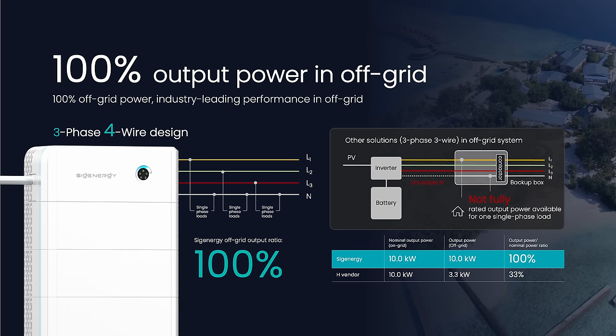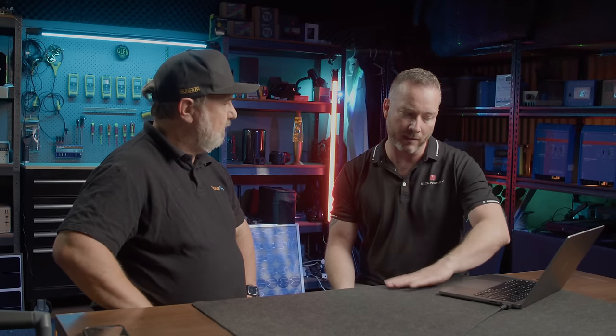Another thing that we've got is 100% output power in off-grid mode. We actually have a three-phase four-wire design, which also has an additional neutral wire coming in. A lot of other systems don't have that neutral wire, so they might have up to only 33% of their output power backed up. So it's true three phase - it can run three phase motors.